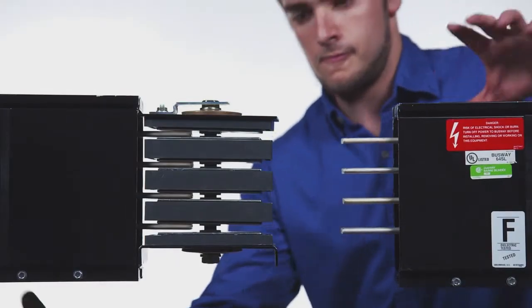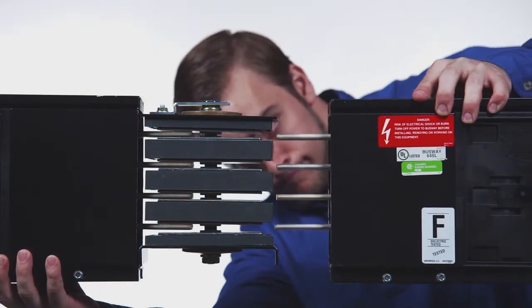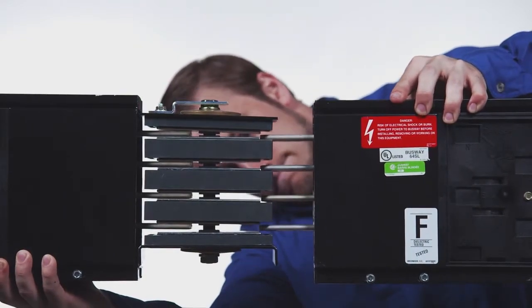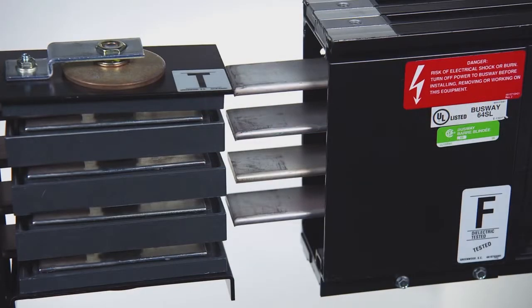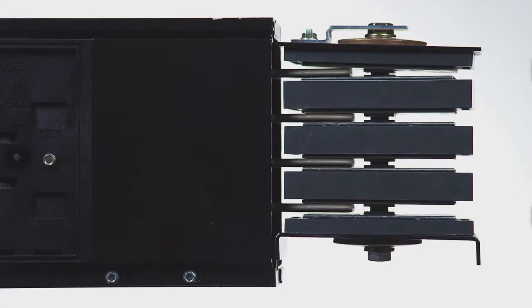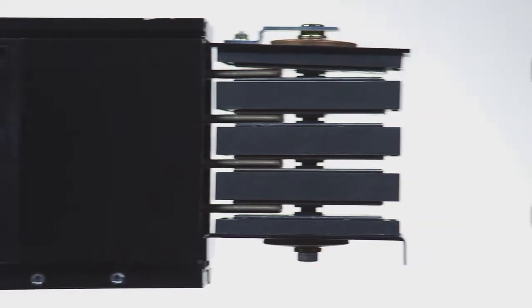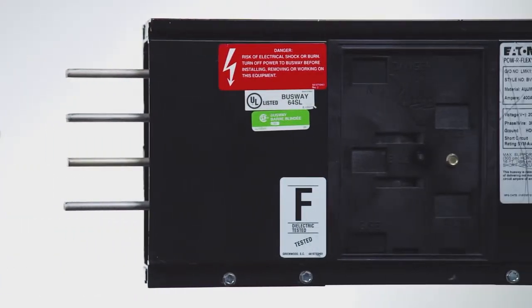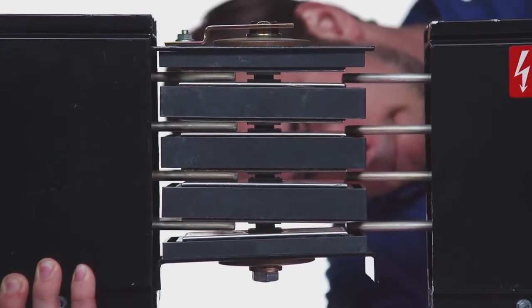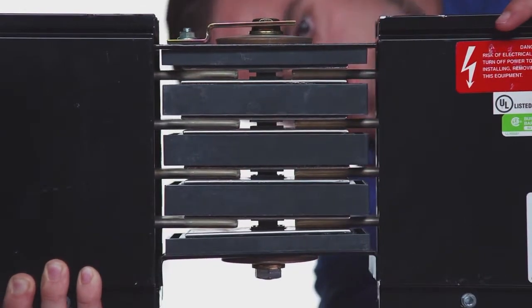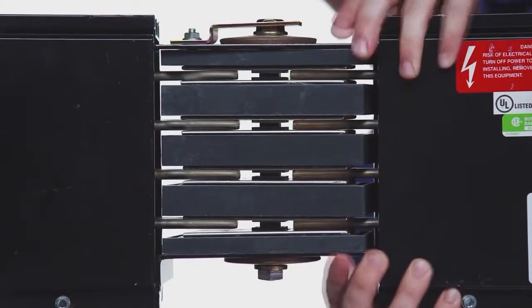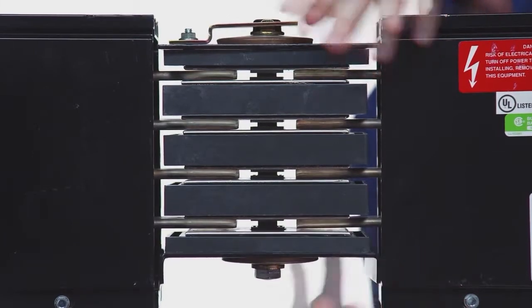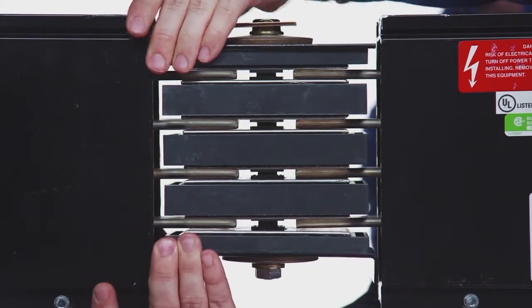To begin the joint installation, align the left end of one section with the right end of the adjoining section. Make sure that the F and T labels are aligned. One end will have a power bridge joint installed, and the other will be a conductor end. Slide the conductor end into the joint end. To avoid insulator damage, make sure the phase conductors are properly seated within the bridge joint.